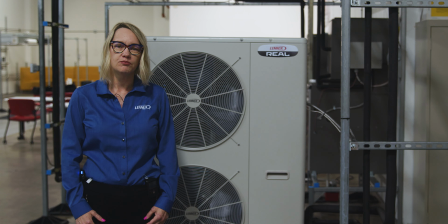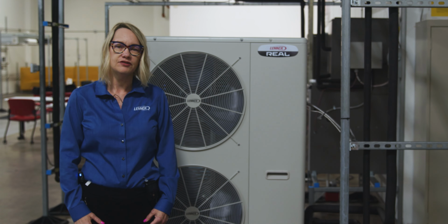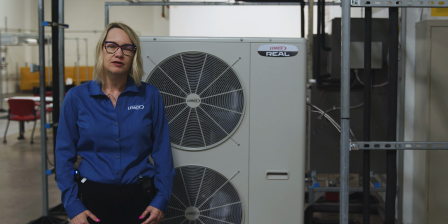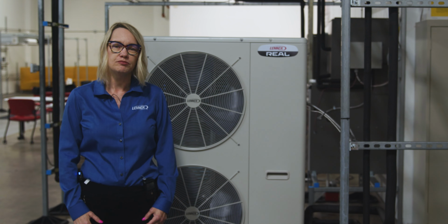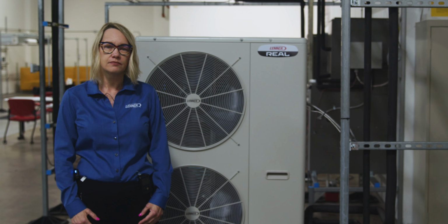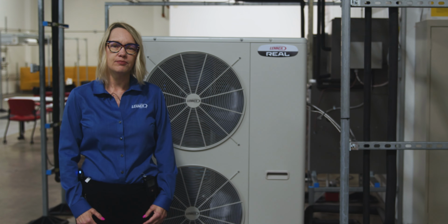Always flow nitrogen when brazing. Flowing 3 psig of nitrogen through the piping when brazing prevents oxidization, which may block the refrigerant piping. Piping lengths dictate pipe sizes.